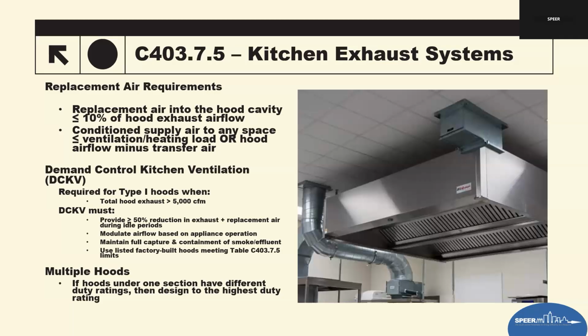There are exceptions. They're called low flow UL 710 rated hoods. These hoods have a maximum airflow of less than or equal to 250 CFM per linear foot, and having a total exhaust of less than 5,000 CFM are exempt. These are specialty lower flow hoods that inherently reduce energy use. Number 2 exception is an ERV. ERVs are allowed when the SRE is greater than or equal to 40%, and its airflow is greater than or equal to 50% of its total exhaust. This allows kitchens to recover some of the heat from the exhaust air under certain mechanical code conditions.